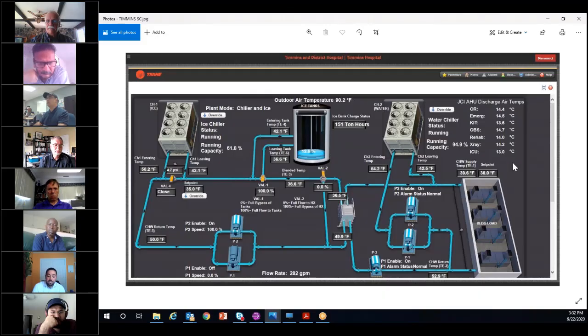The hospital is certainly seeing lower electricity bills by using as much off-peak, or by shifting as many off-peak kilowatts as possible, and minimizing the on-peak kilowatts. They're definitely saving anywhere in the, I'd say, 30 to 40% of the utility costs specific to this system. Of course, not for the whole hospital, but specific to the usage of this chilled water system.